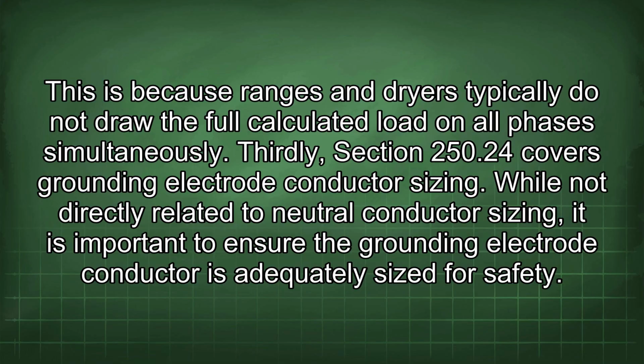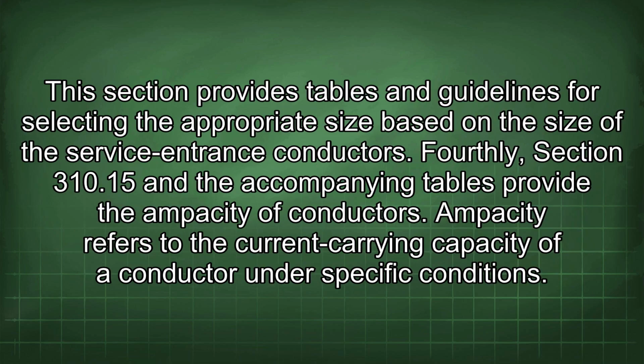Thirdly, Section 250.24 covers grounding electrode conductor sizing. While not directly related to neutral conductor sizing, it is important to ensure the grounding electrode conductor is adequately sized for safety. This section provides tables and guidelines for selecting the appropriate size based on the size of the service entrance conductors. Fourthly, Section 310.15 and the accompanying tables provide the ampacity of conductors.